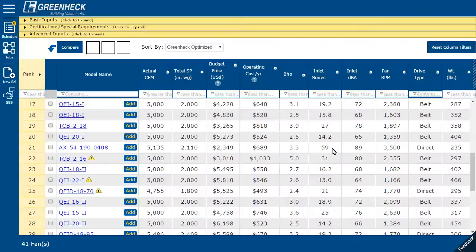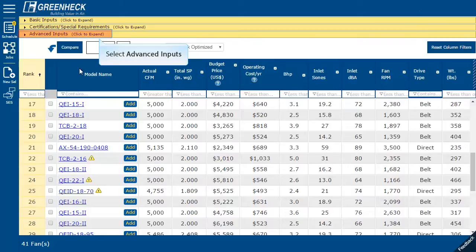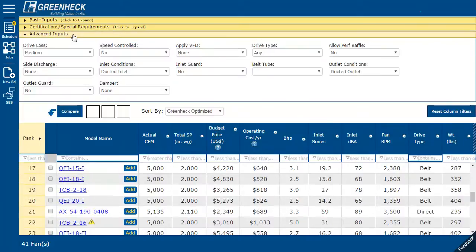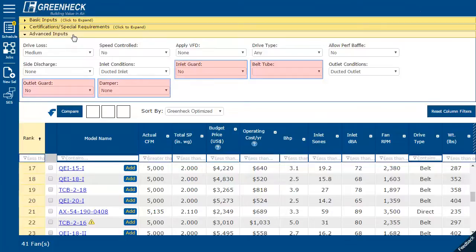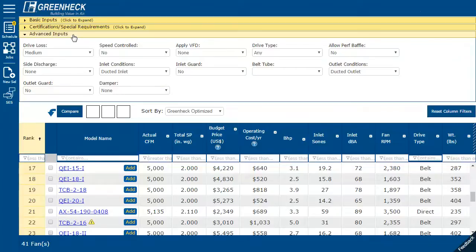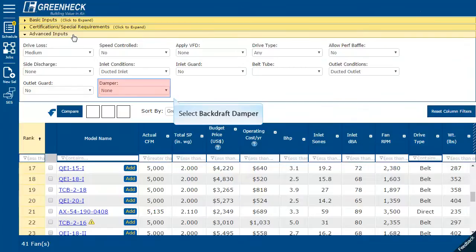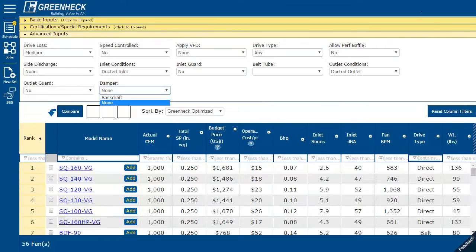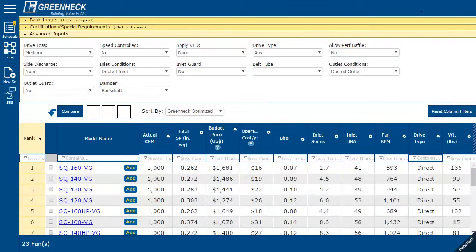To expand on the concept of keeping you out of trouble, we added performance corrections. Fan manufacturers offer fan accessories, many of which affect the fan's performance. Most fan manufacturers ignore their effects, resulting in poor test and balance results. E-CAPS takes into account the pressure losses for backdraft dampers, guards, and many more. Basically, we add some internal static pressure to increase the total static pressure.